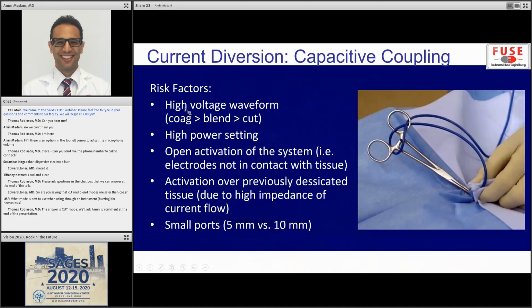Other things to avoid: avoid high voltage, so don't use coag if you don't need to. Avoid high power settings, and don't use open activation. Also, don't activate over previously desiccated tissue, because that charred tissue you keep burning is just an insulator — it's like activating in open air.